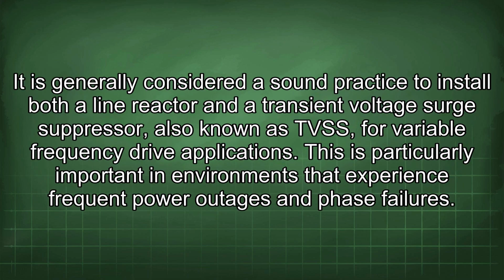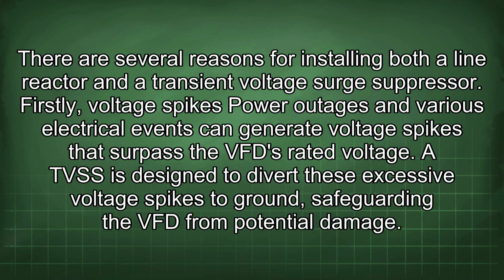It is generally considered a sound practice to install both a line reactor and a transient voltage surge suppressor, also known as TVSS, for variable frequency drive applications. This is particularly important in environments that experience frequent power outages and phase failures. There are several reasons for installing both a line reactor and a transient voltage surge suppressor.